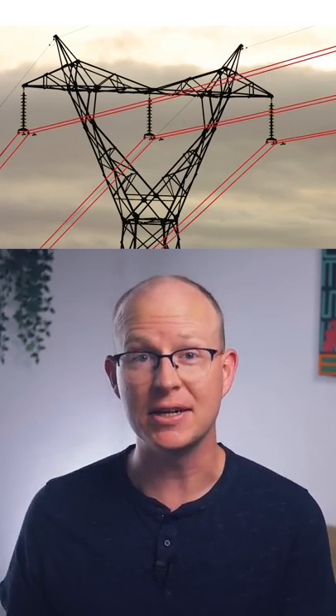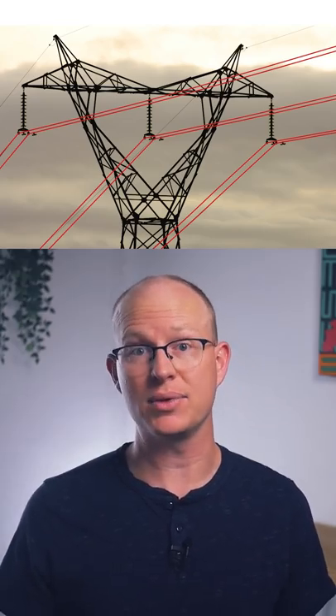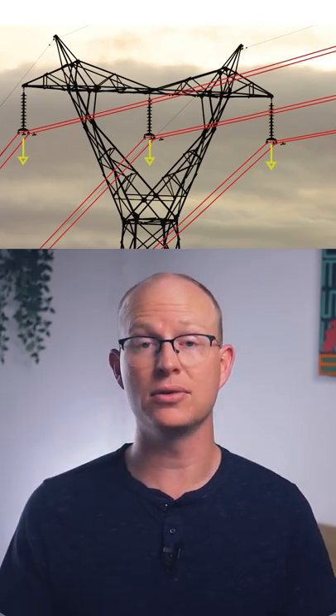Most electrical transmission towers are suspension structures, where each conductor hangs vertically from a single insulator. The forces they have to withstand are mostly just the vertical loads from gravity.